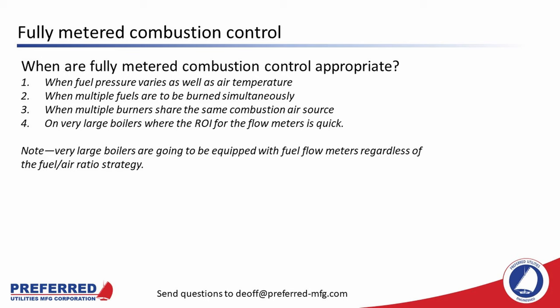Fully metered combustion control reacts faster to upset conditions because flow meters have a much faster response time than an oxygen analyzer. But oxygen trim is usually incorporated into fully metered controls anyway as a bias to the air signal, providing the safety advantage of a low oxygen trip. Most of Preferred's fully metered combustion control systems are done in our loop controllers, now the PCC-4. We can also program the same control strategy into a PLC. However, the least expensive way to get fully metered combustion control is with the industrial version of our BurnerMate Universal — it can be set up for fully metered combustion control and uses canned software that is UL-listed and FM-approved.